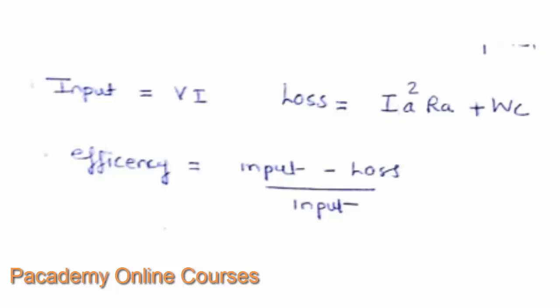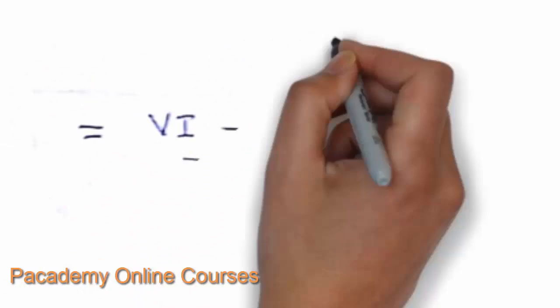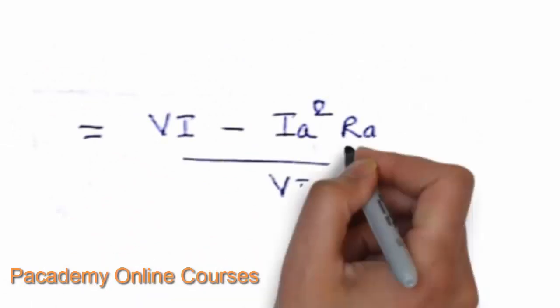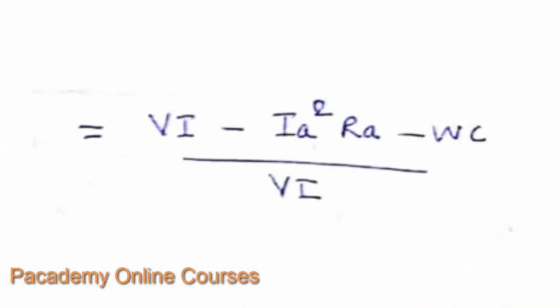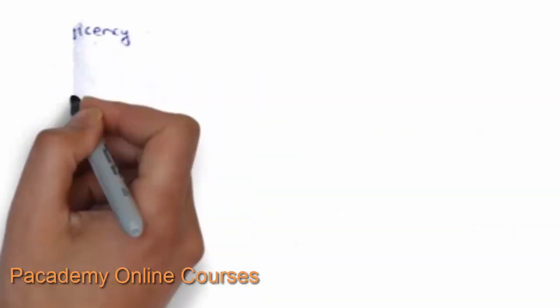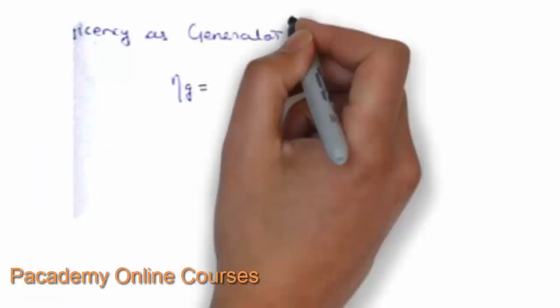This is an easy method to find the efficiency of shunt machines, performed during the testing phase before commissioning to find rated values. The motor efficiency can be written as: (V·I minus IA squared·RA minus WC) divided by V·I, where V is the supply voltage and IA is the armature current supplied to the motor.